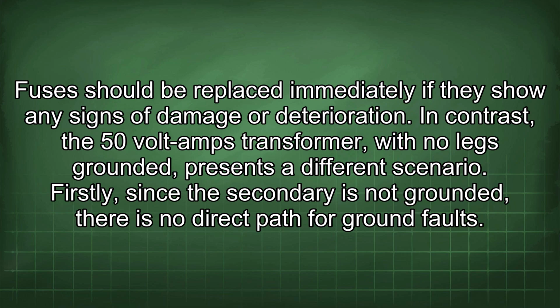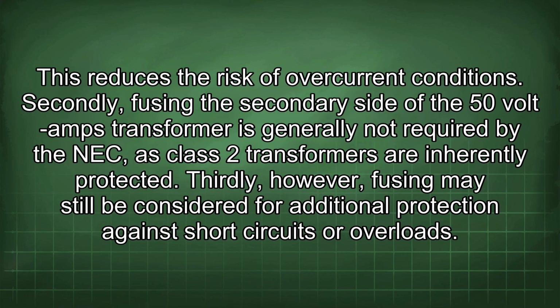In contrast, the 50 volt-amp transformer, with no legs grounded, presents a different scenario. Firstly, since the secondary is not grounded, there is no direct path for ground faults. This reduces the risk of overcurrent conditions. Secondly, fusing the secondary side of the 50 volt-amp transformer is generally not required by the NEC, as Class 2 transformers are inherently protected.